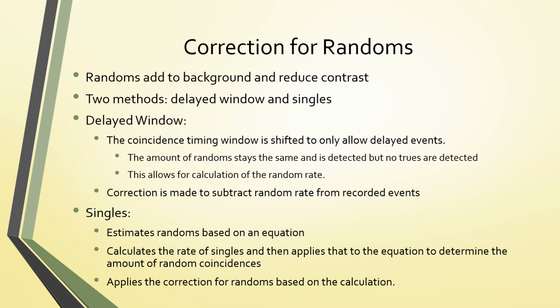So there are two methods. One is a delayed window and the other is singles. With the delayed window, the coincidence timing window is shifted to only allow delayed events. The amount of randoms stays the same and is detected, but no trues are detected. This allows for calculation of a random rate. And then that random rate is subtracted from the recorded events. Singles are estimates of randoms based on an equation. It calculates the rate of singles and then applies that to the equation to determine the amount of random coincidences. This applies the correction for randoms based on a calculation.